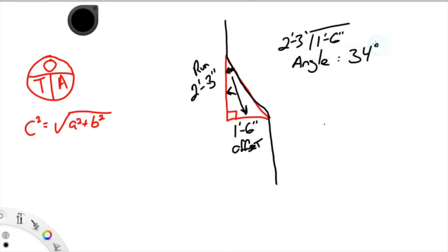34 degrees, and that is 34 degrees on both sides, since it's parallel. If this were perpendicular, it'd be different. You'd have to subtract 34 from 90, and that would tell you what that degree is if it were perpendicular. So we'll have to solve a takeoff for that fitting. We've got our travel to solve. We've got our cut piece or end-to-end measurement to solve, and that should do it.